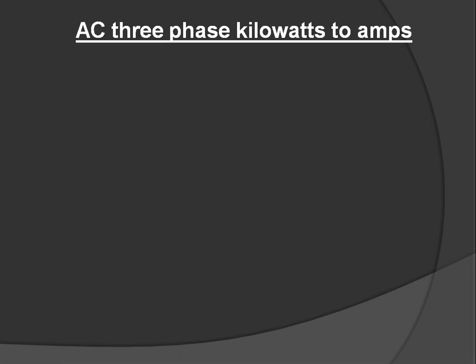The second one is kilowatts to amperes in AC three phase. The formula is I equals 1000 multiplied by P, divided by root three times PF times V.